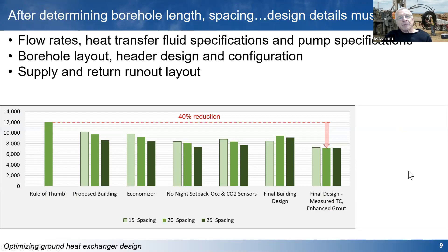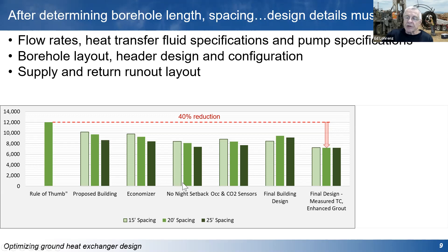As we looked at in the previous session in August, the amount of pipe needed in the ground varies pretty significantly. You have the opportunity to work with architects, engineers, and building owners to make changes. For example, putting an economizer in the system to supply fresh air or cooling using outside air, or having a night setback, can make a big difference. Looking at occupancy and CO2 sensors to minimize the impact of fresh outdoor air — the final design for a 24,000 square foot building was reduced from about 12,000 feet of borehole down to about 7,000 feet.